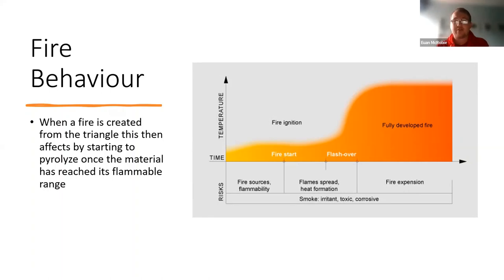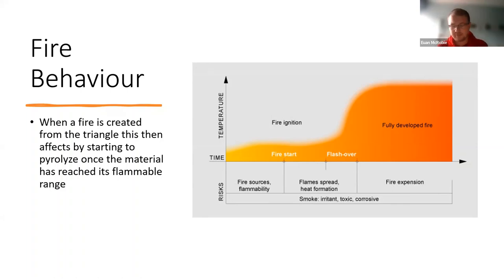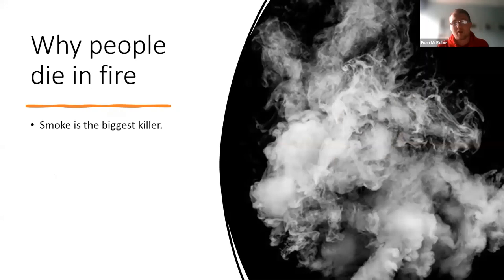Then we get what we call flashover, which I'll explain shortly. After that, there's a fully developed environment within the compartment, followed by the decay stage. When a fire can't pyrolyze any more material, it will start to die because it no longer has that perfect fire triangle mixture. If we can remove an element — like fuel or material stores — it prevents fire spread.